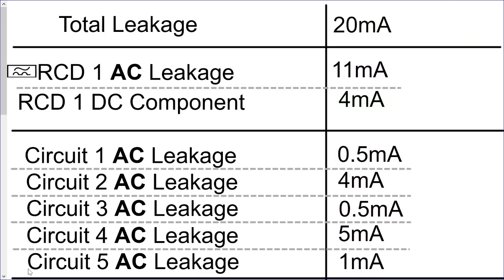So once you've got all those values, you'll see there the total leakage that we got at the start. We got 20 milliamps. Obviously, we've only got 2 RCDs. We're expecting a maximum of 18 milliamps combined between those 2 residual current devices. So we're going to have to investigate this non-compliance.